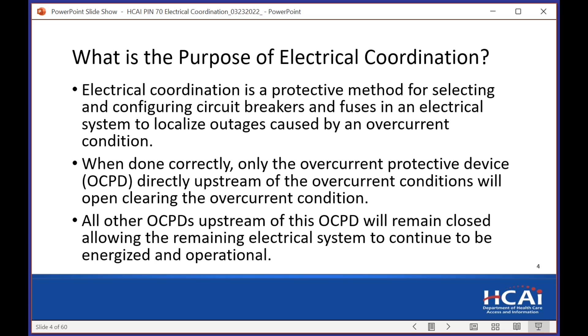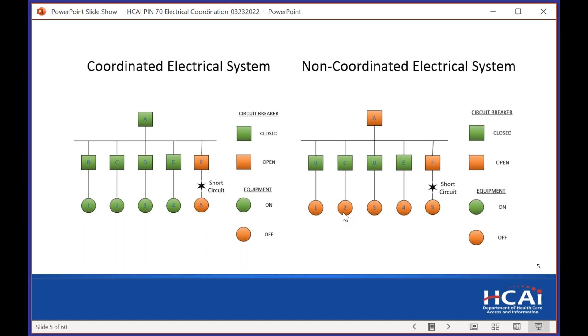So let's look at a picture. On the left, we have a coordinated system. We have this unit number 5. There's a short in the cable going to it. It opens breaker F. And as you see, breaker A does not open because F is coordinated with A. The remaining pieces of equipment, 1 through 4, stay energized. In a non-coordinated electrical system, a fault on this feeder will open A and F, and will lose power to the other equipment connected to this panel.